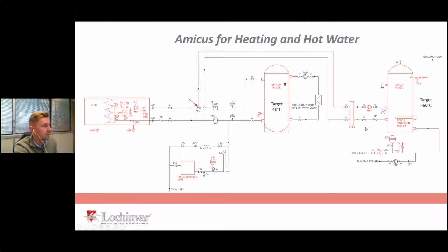will then trigger a live from its panel, switch a motorized three-port valve, and increase its flow temperature to 63 degrees centigrade for a short period of time. And when it flows at 63 degrees centigrade, the secondary pump will come on and top your hot water tank back up to 60 degrees, which is great. So you've got 60 degrees back in your potable hot water vessel. The BTS sensor, your sanitary hot water sensor, is now satisfied, so it drops its live, the heat pump turns its three-port valve back to the original position and goes back to its normal life of serving the heating system.